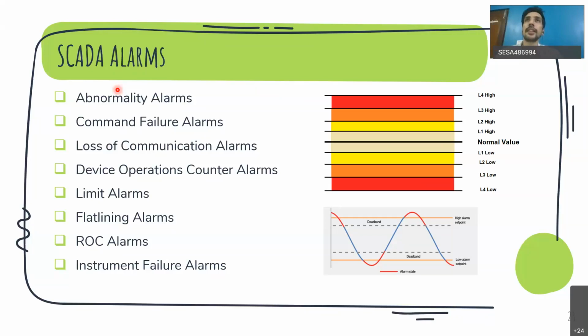Like you are managing an 11 kV network, so voltage can go say from 11 to 11.2 or 10.7, but suddenly it shot up to 15 or 16. So that is not good. Those kinds of things are shown by these rate of change alarms. Similarly, instrument failure alarm. Generally your measuring instrument will have some measuring range. Say for example, the voltage can be in the range of 11 kV, but suddenly it shows 66 kV. So something is wrong with the measuring instrument. At that time this kind of alarm will get generated. And there are many other types of alarms as well. At a high level, these are the different types. Okay.